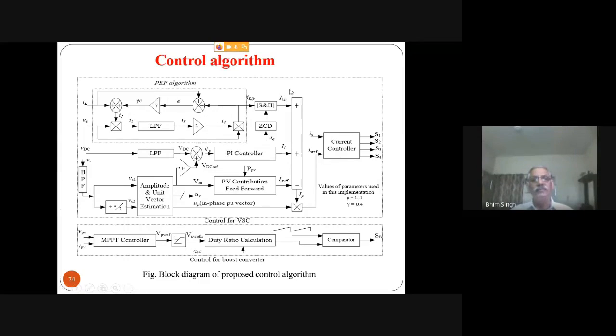This phase template is used for extracting the fundamental on the load current, for only the active component of current. We use a zero crossing detector with the help of quadrature, at zero crossing of the quadrature with the voltage, which is required for sample and hold to get the amplitude only for the active component of current from this fundamental current.